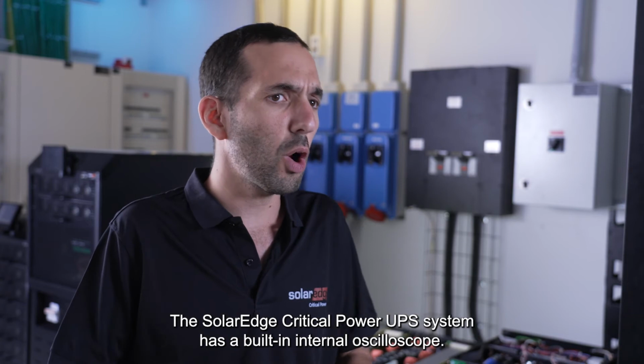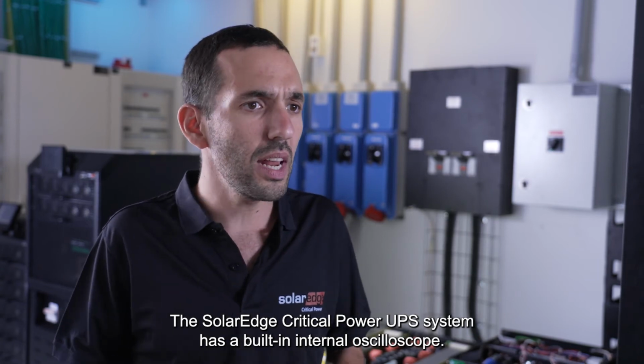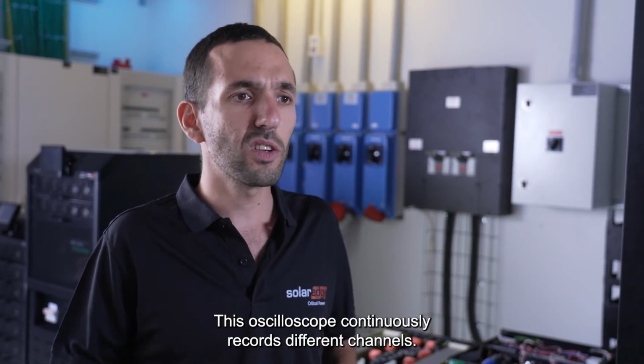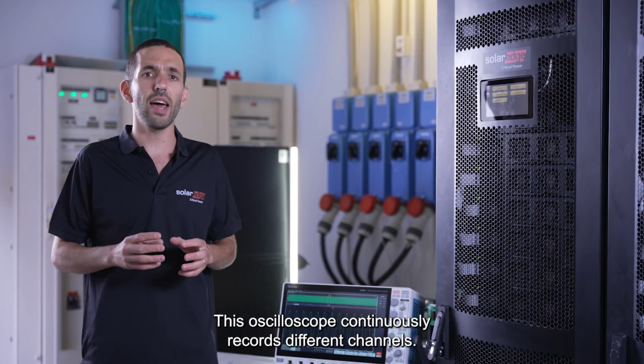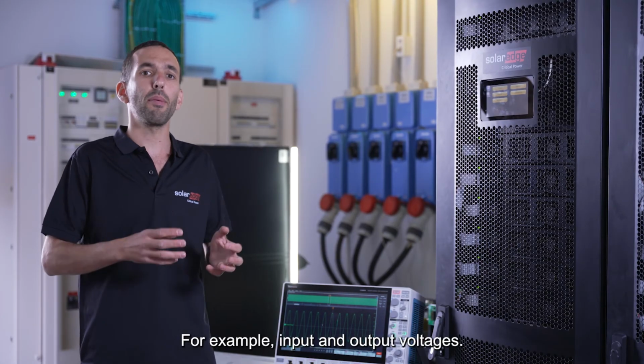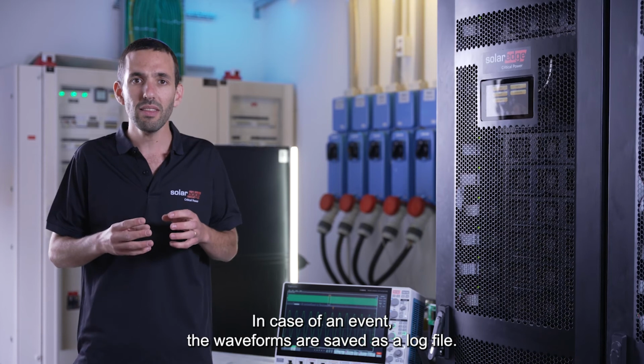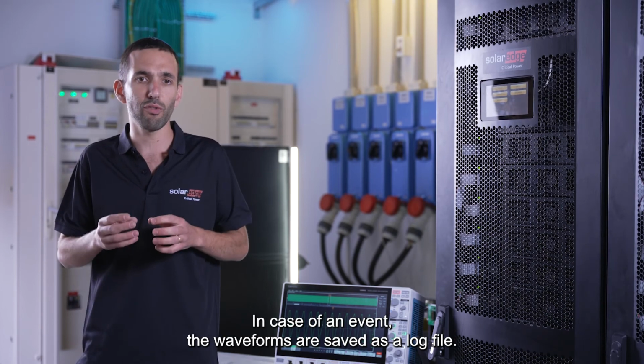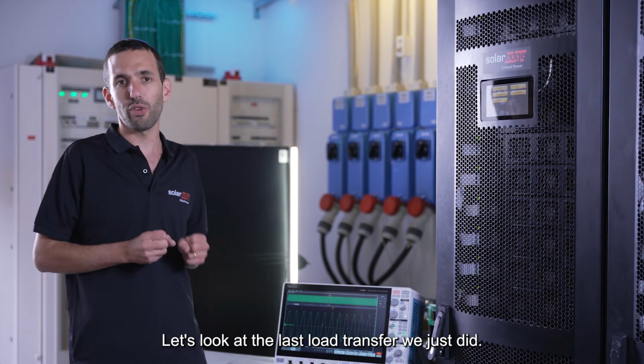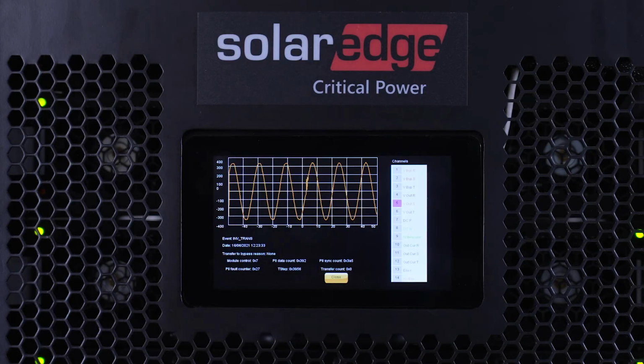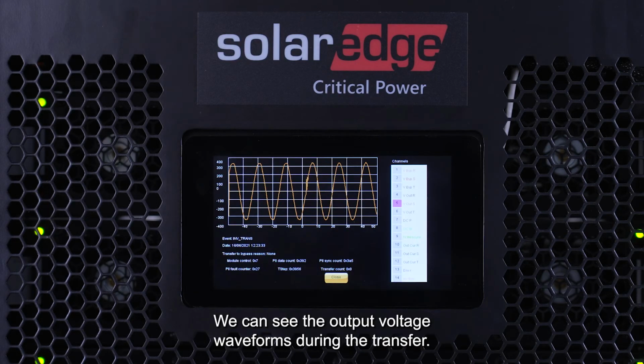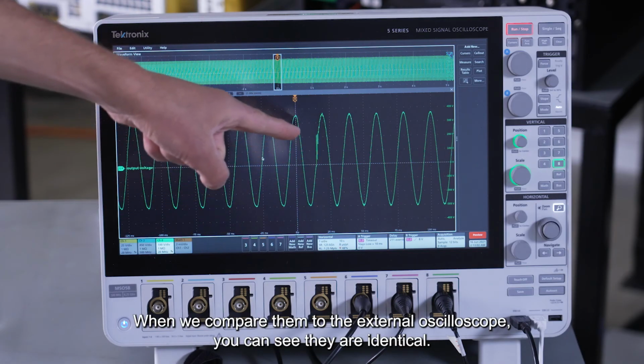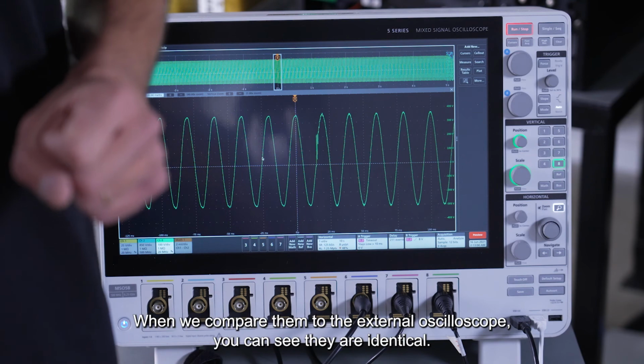The SolarEdge Critical Power UPS system has a built-in internal oscilloscope. This oscilloscope continuously records different channels, for example, input and output voltages. In case of an event, the waveforms are saved as a log file. Let's look at the last load transfer we just did. We can see the output voltage waveforms during the transfer. When we compare them to the external oscilloscope, you can see they're identical.